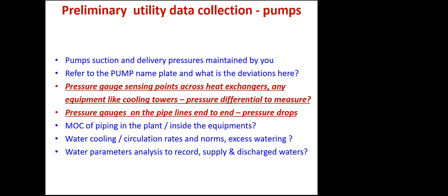So these are the preparations you have to do. For the cooling tower or the heat exchangers, we concentrate more on the pressure because an excess pressure drop on a cooling tower shows that the polyfills in the cooling tower are getting choked. Or the pressure difference across a heat exchanger: once the line gets choked and its diameter is reduced, the pressure differential automatically goes up. The temperature differential is a matter of concern for efficiency, whereas the pressure differential across the blower, cooling tower or heat exchanger is a matter of concern for the health of the machines.